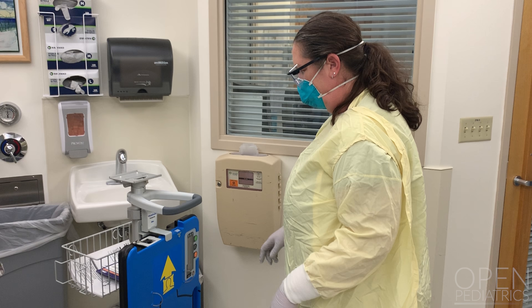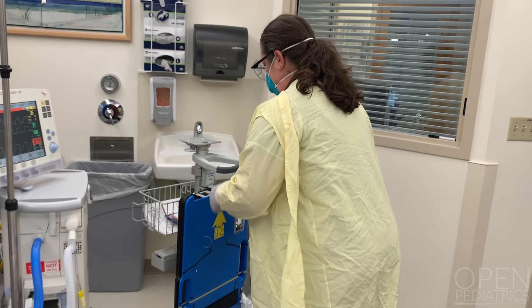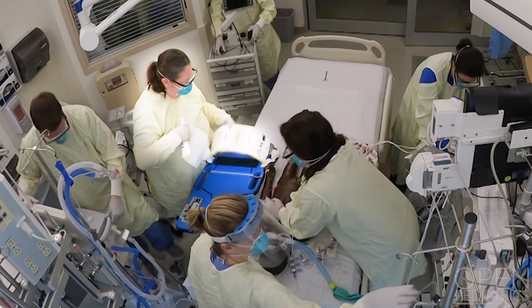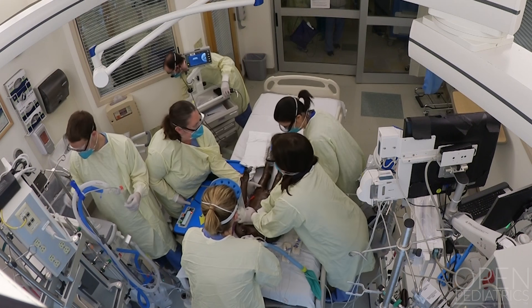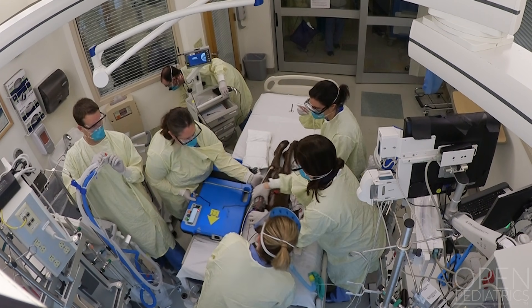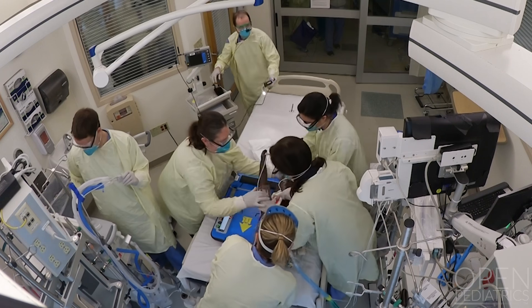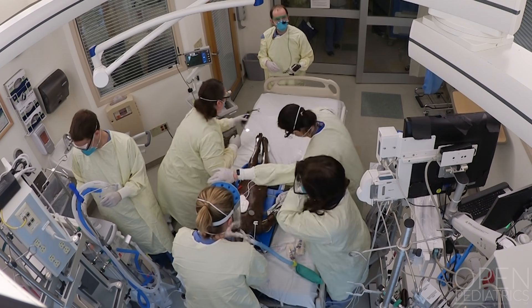To rapidly deploy the mechanical CPR device, when lifting off the stand, turn on the device by pressing the on/off button at the head end of the platform. The compression band is opened by separating the Velcro sides. Either the mechanical CPR device or a backboard is placed by log rolling the patient and sliding the board under. While the back is exposed, the posterior defibrillation pad is placed. Manual compressions are then resumed, and the anterior defibrillation pads are then placed.